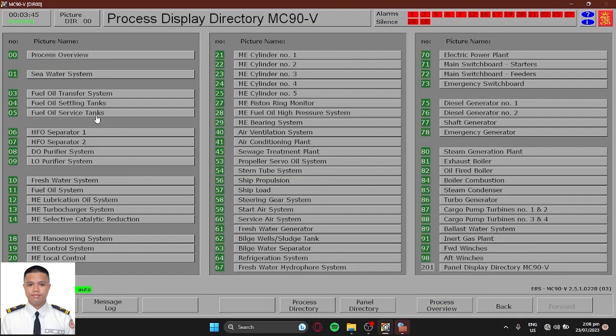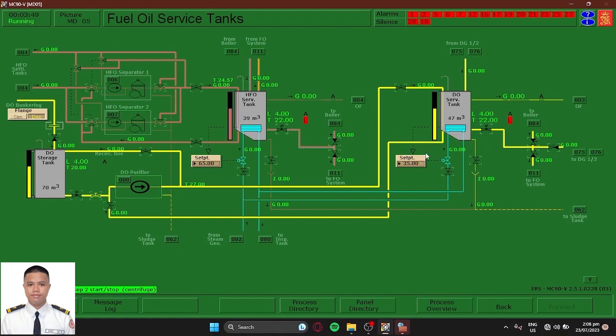Go here to our fuel oil service tanks, 05. Focus here on the diesel oil. So the first thing we're going to do here is to drain this, just to remove the water accumulated at the bottom of the tank. Once it says G15 here, close the drain. Line up the valves leading to DG1 and 2.